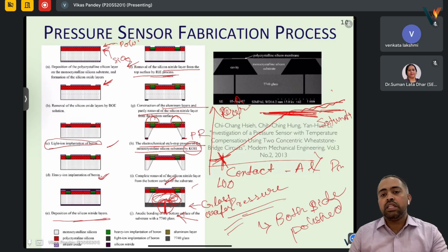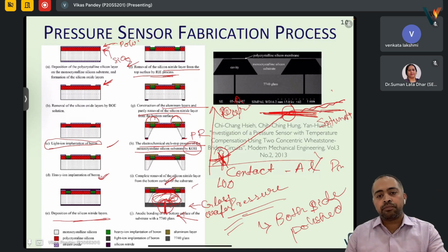That point we call the saturation point of the sensor. If you keep continuing even after that, it might break, it might burst. So that point we generally don't go for. Our point of concern is between LOD and the saturation point. So we define our range based on this.